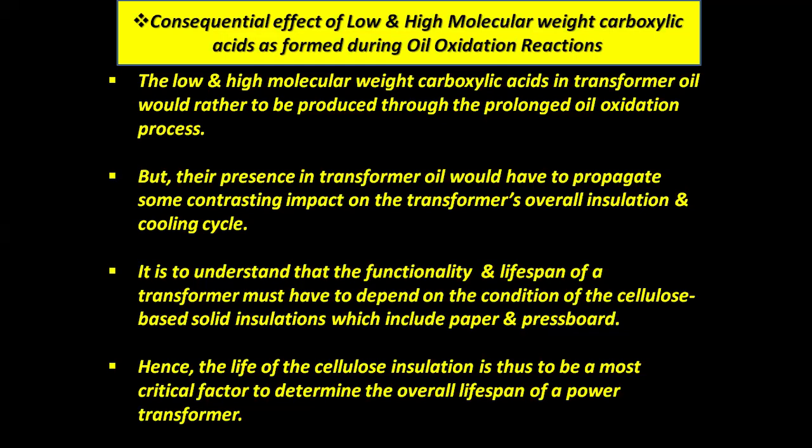The functionality and lifespan of a transformer depend on the condition of the cellulose-based solid insulations, which include paper and pressboard. Hence, the life of the cellulose insulation is the most critical factor in determining the overall lifespan of a power transformer.